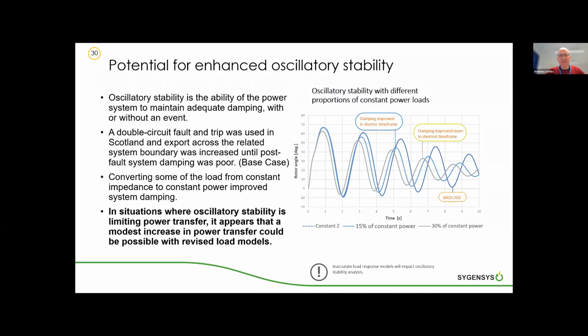The third area we looked at was oscillatory stability, and this is the ability of the power system to maintain adequate damping with or without an event. Again, we used a double circuit fault and trip in Scotland with data supplied by ESO and increased export across this boundary until we had poor damping post-fault. And this is the base case curve here, the dark blue line. Then, as before, we converted 10% or 15% in this case, to 30% of the load to constant power. And again, unexpectedly, we found that the damping actually increased, damping improved on the system. So again, in cases where oscillatory stability is the limiting factor, there may be some modest improvement of power transfer possible by including some constant power load models in the network.